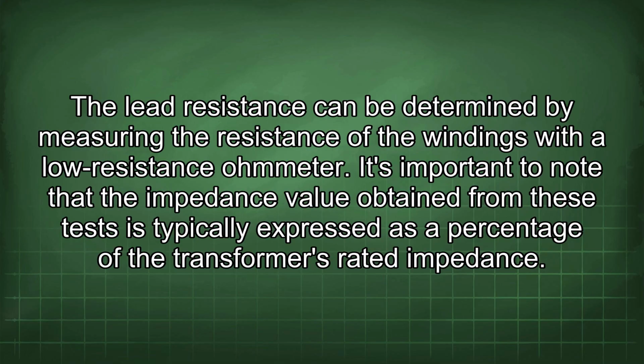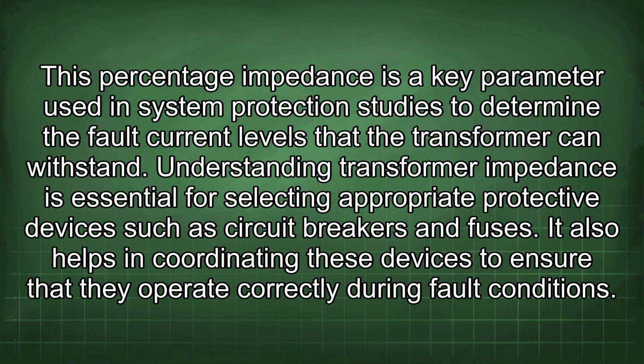It's important to note that the impedance value obtained from these tests is typically expressed as a percentage of the transformer's rated impedance. This percentage impedance is a key parameter used in system protection studies to determine the fault current levels that the transformer can withstand. Understanding transformer impedance is essential for selecting appropriate protective devices such as circuit breakers and fuses. It also helps in coordinating these devices to ensure that they operate correctly during fault conditions.